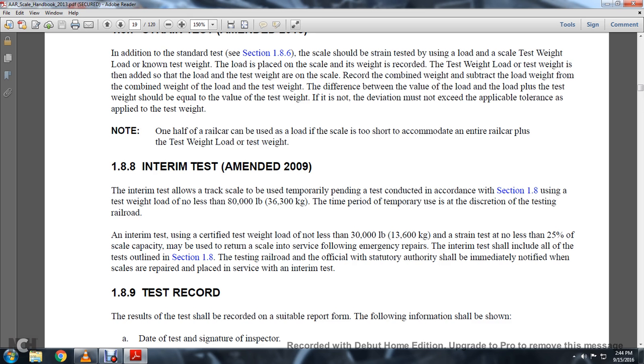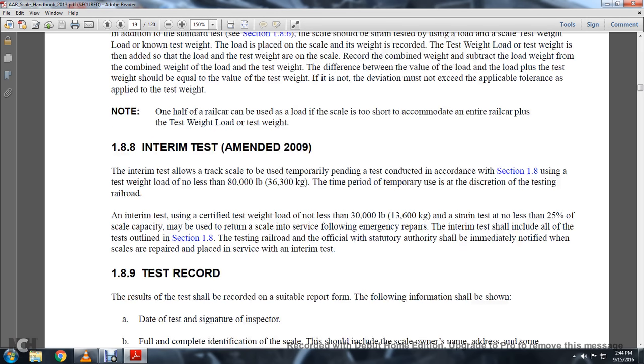1-8-8: Interim Testing, Amended 2008-09. Interim testing allows the track scale to be temporarily placed in service depending on the test conducted within the scope of Section 1-8, using a test weight load of no less than 80,000 pounds. A time period of temporary use is at the discretion of the testing railroad. Interim test using a certified test weight load of no less than 30,000 pounds and a strain test at no less than 25% of scale capacity may be used to return the scale to service following emergency repairs.